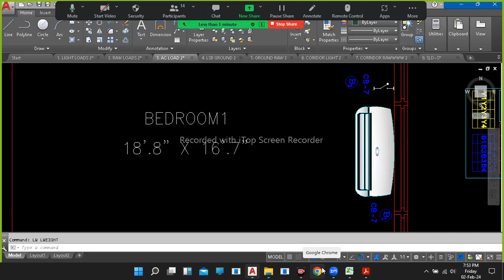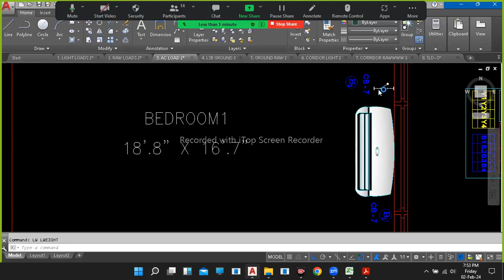MCB? Yes, we'll get a 2-pole MCB enclosure - I'll show you. In enclosures the market will provide 2-pole MCB enclosures. If it's a single pole, if you're only placing single pole, then only phase is controlled and neutral will be directed, but definitely we don't go with that - we go with the 2-pole enclosure. We'll place a 2-pole MCB of 16 amps. Here we'll be providing 16 amps, in the DB also we'll have 16 amps, and even beside the AC we'll have 16 amps.